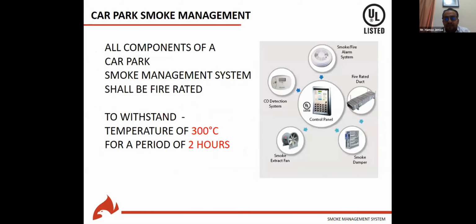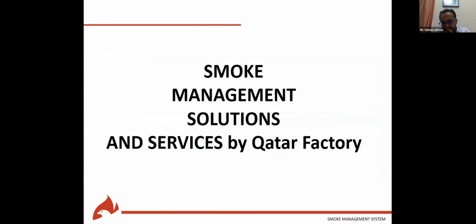As you can see, all the components of the smoke control of car park ventilation are working in communication with each other: the smoke and fire alarm system, the heat detector, the smoke detector if it is there in the car park, the CO detection system, the smoke extraction fans, the ducting system if it is using duct, and jet fans if the system uses jet fans. All the components should be fire rated for 2 hours and 300 degrees as per the regulation of the civil defense.